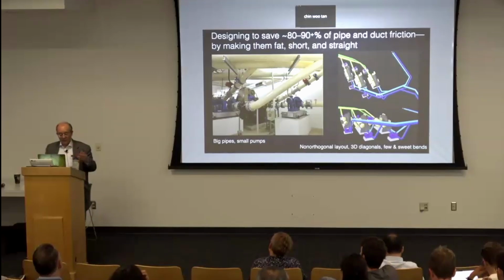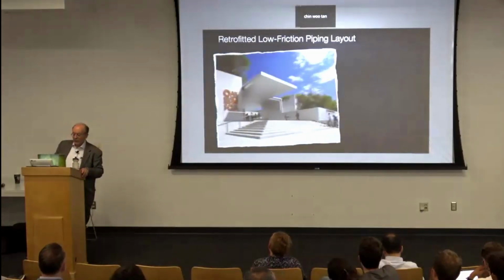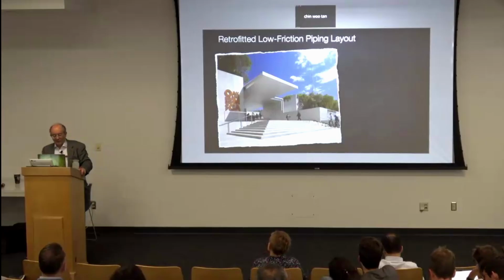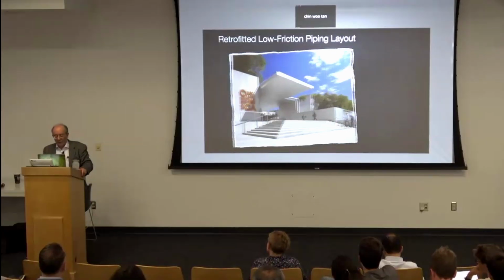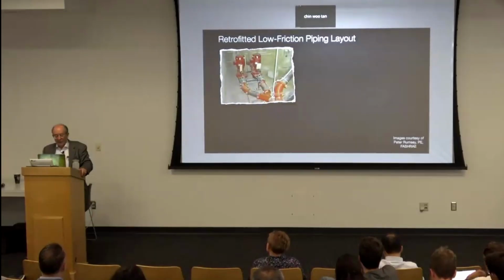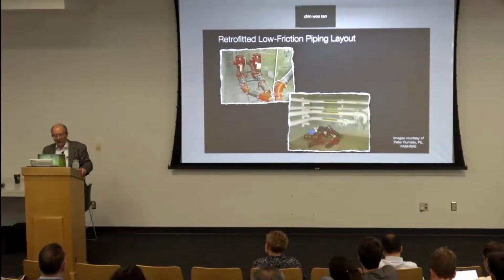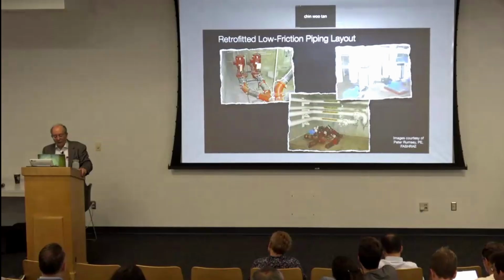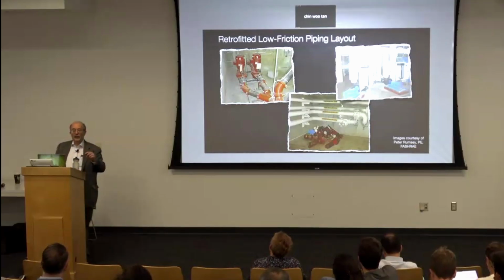Probably no climate models even compete or compare efficient use with more supply, let alone look at this kind of design. At the Oakland Museum, our treasured Stanford lecturer colleague Peter Rumsey retrofitted an efficient piping layout that cut the pumping energy by three quarters with a 2 or 3 month payback, and eliminated 15 pumps that will never again waste energy and maintenance costs. Repiping another pumping loop and adding variable frequency drives doubled the flow and saved 85% of the energy. Peter simply asked the pipe fitters to lay out the supply pipes as if they were drains.